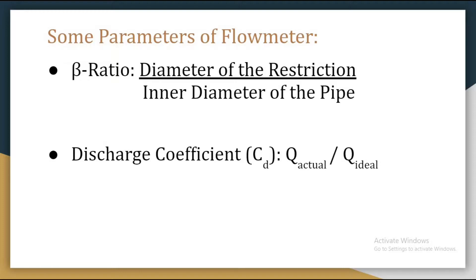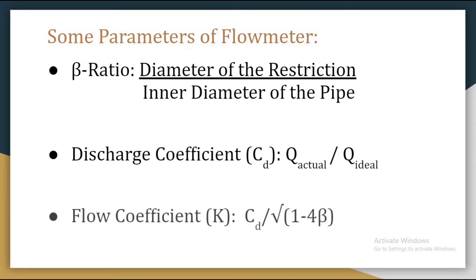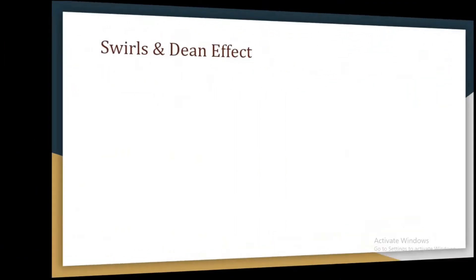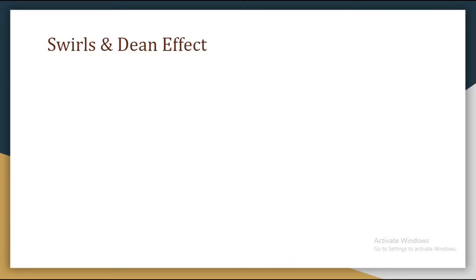The next parameter is discharge coefficient. Discharge coefficient is the ratio between actual volumetric flow rate and the ideal volumetric flow rate. The higher the discharge coefficient of a flow meter, the better it is, because it is closer to the ideal flow rate. The next one is flow coefficient, given by k equals cd divided by the square root of (1 minus beta to the power 4). If we know the discharge coefficient and beta ratio, we can easily find the flow coefficient.